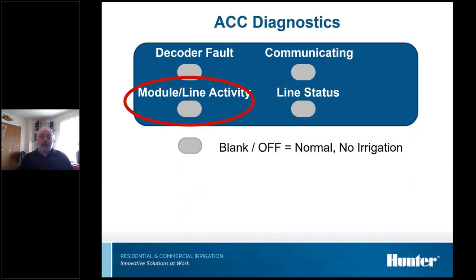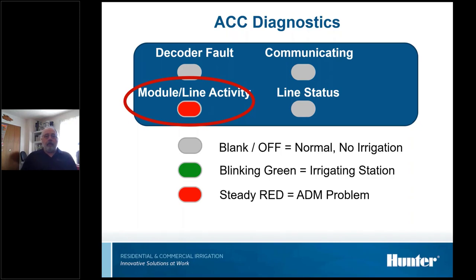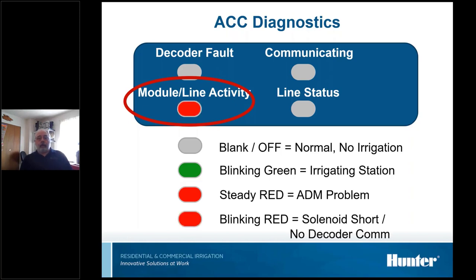The line activity light, again, blank is normal. It's not doing anything when there's nothing going on. It blinks green when it's irrigating. And steady red, again, is telling you that it believes there's a problem with the module. In either case, if you see the red light either blinking or on steady, disconnect the field wires and see what happens to the light. If you disconnect it and the light stays red, the module's bad. But if you disconnect it and the light goes out, you've got a short out in the field somewhere. The same thing, if it's blinking, it says there's a short.